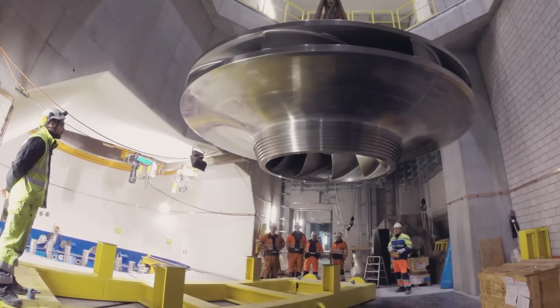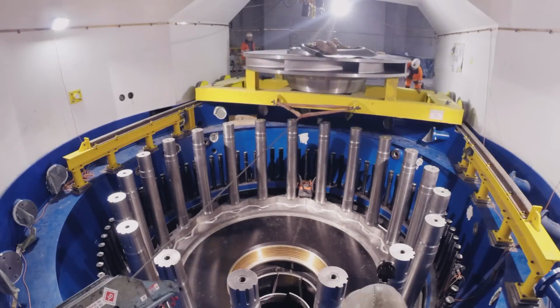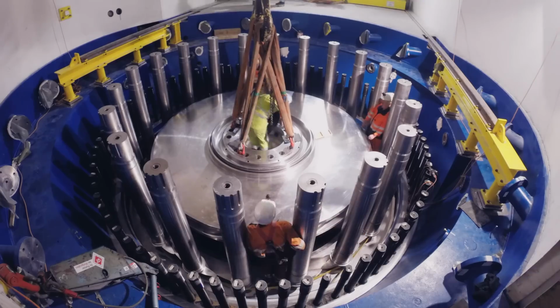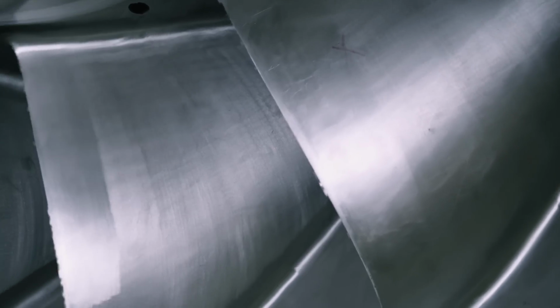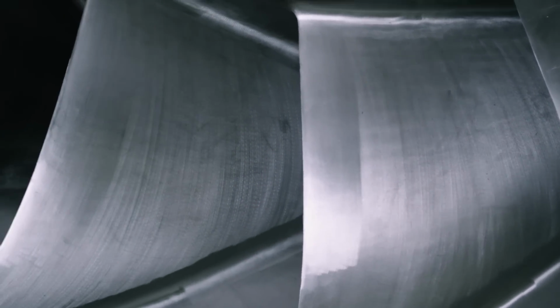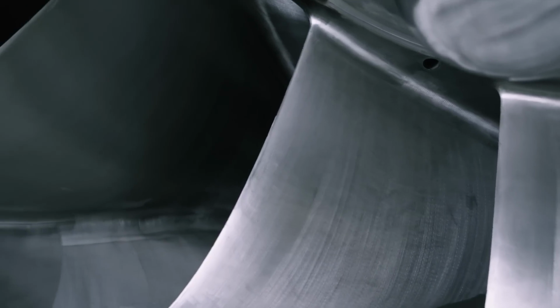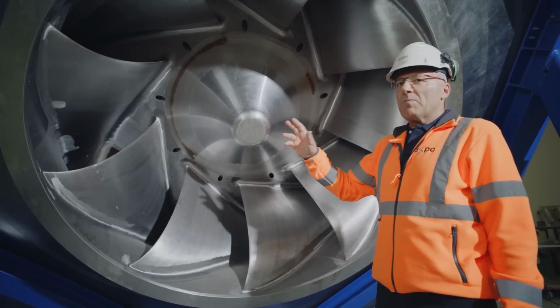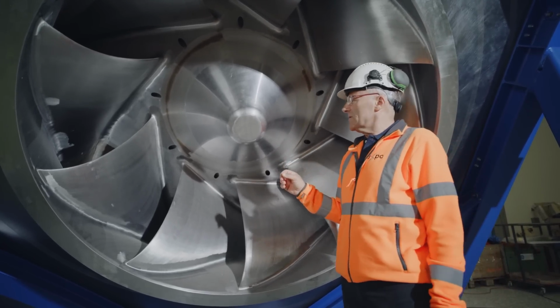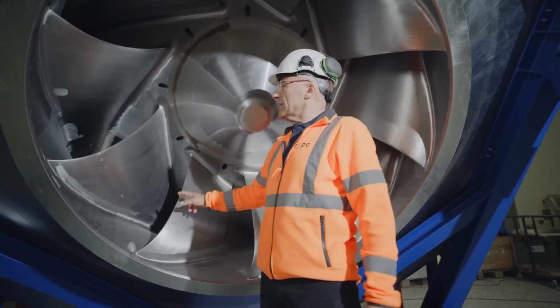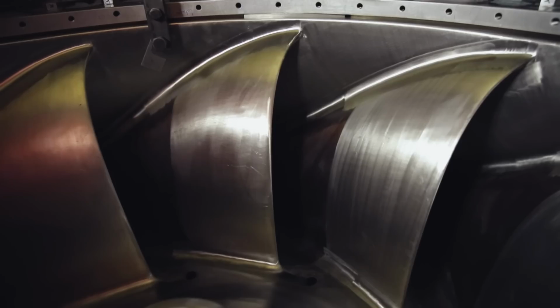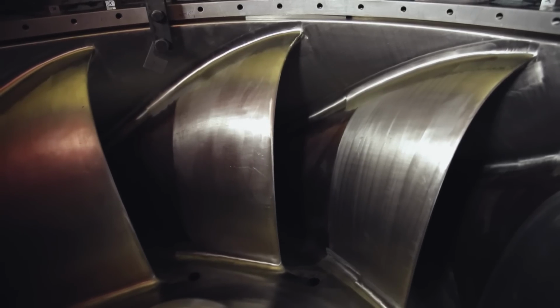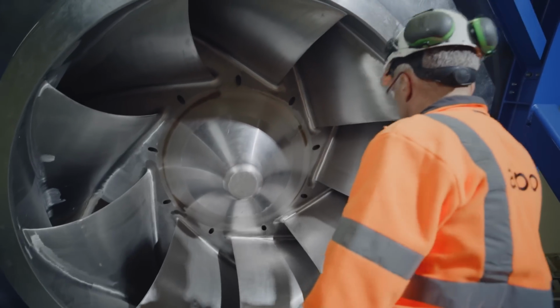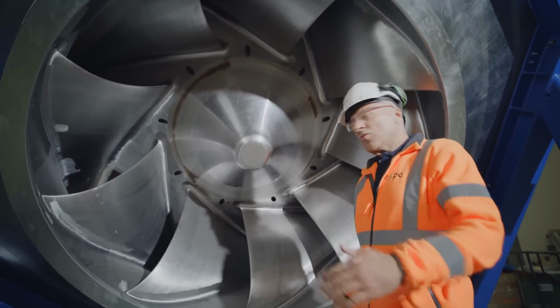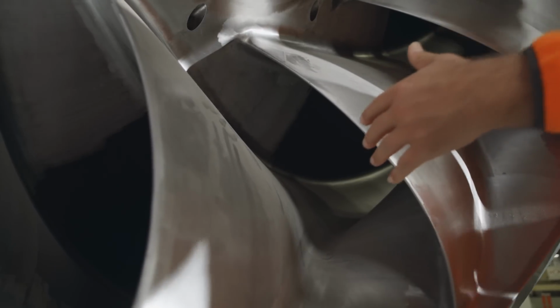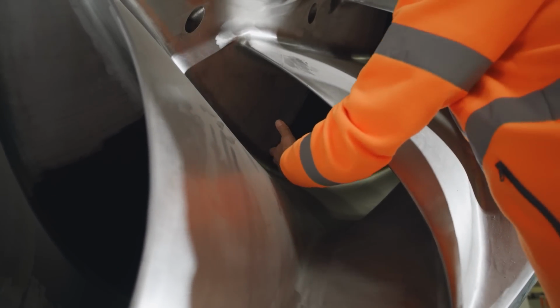First came the enormous pump turbines. As these blades rotate, they transform the kinetic energy of the water into rotational energy. The runner has a power of 250 megawatts, and its design has 9 blades. In pumping operation, the runner turns in this direction, and the flow goes through these channels to Lake Mut to store energy.